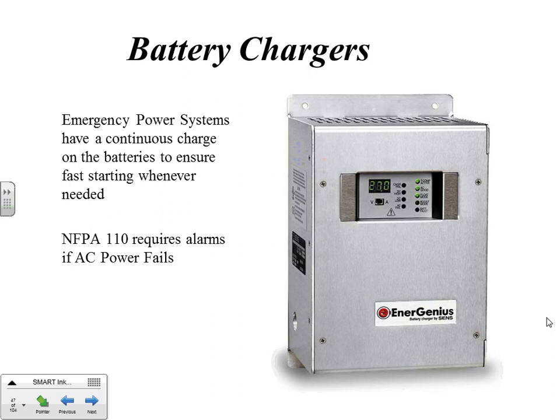Battery chargers, again, if this thing's just sitting, just like a car, you might have a slight drain on the unit all the time if it's connected. If it's not used, it needs something to bump that battery up all the time. So typically we'll have a battery charger plugged in. Just bumps it. This one's a 24-volt charger. Again, an NFPA 110 requirement.